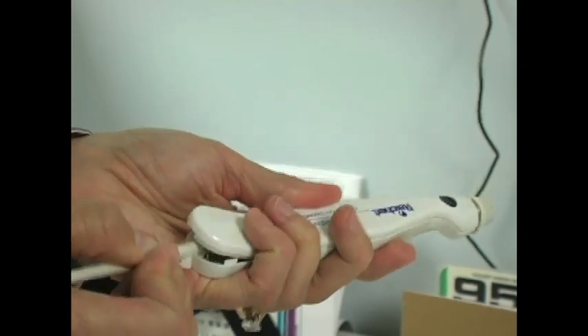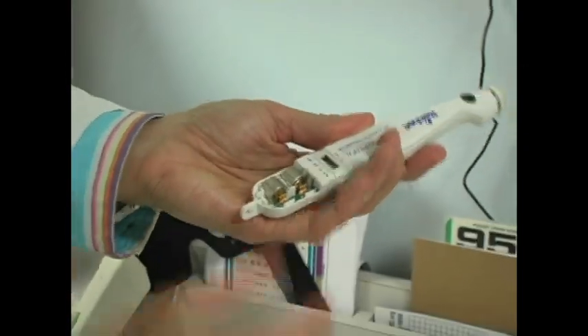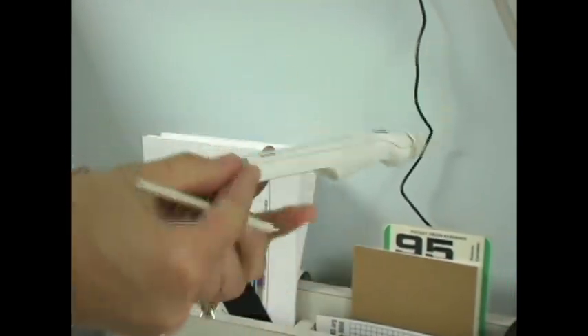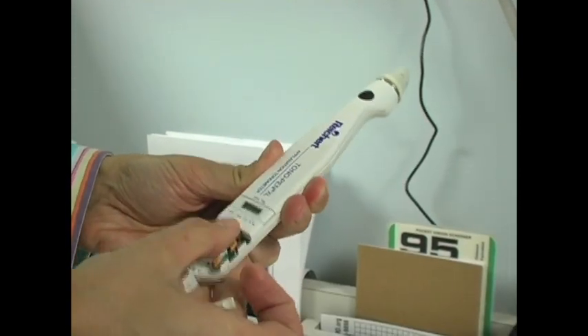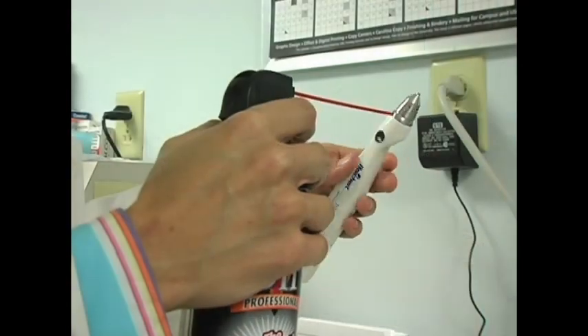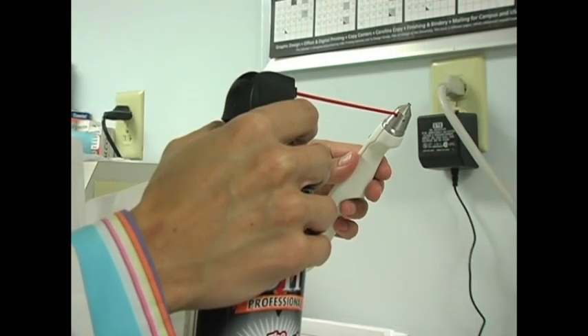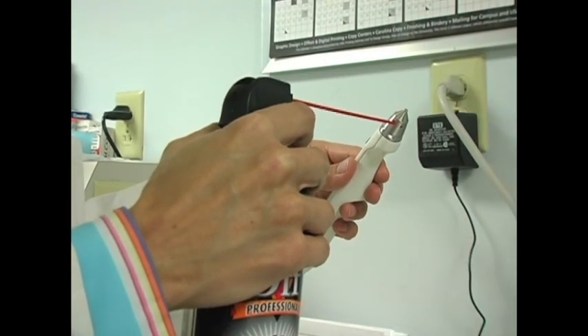Tonopens are battery-operated devices. You should have a regular maintenance schedule for the tonopen, which includes weekly calibration, routine battery changes approximately every 4 months, and cleaning the tonometer tip with compressed air approximately every 2 months. Be sure to keep the air canister vertical, otherwise the liquid propellant would damage the tonopen.